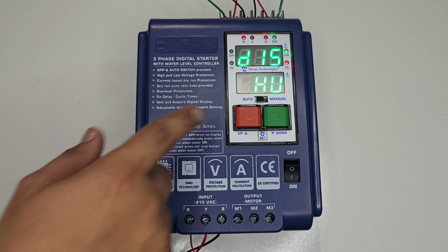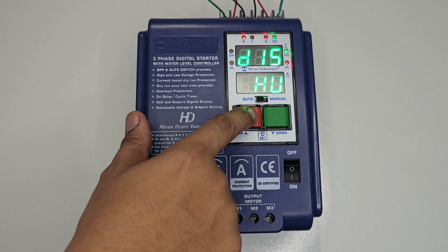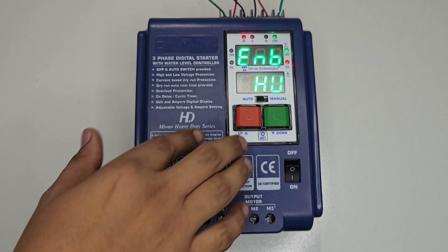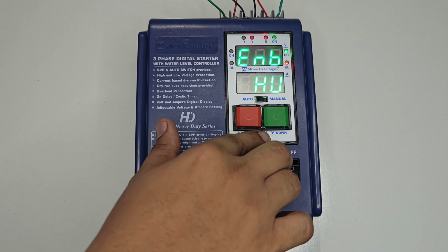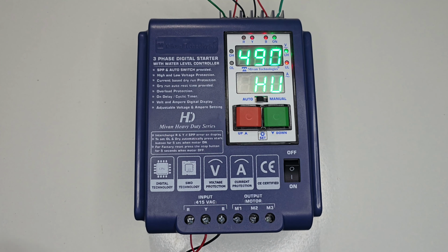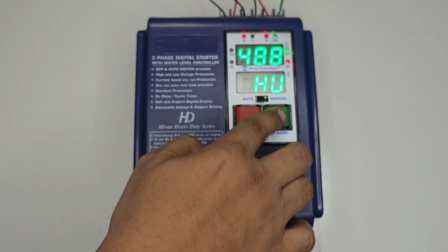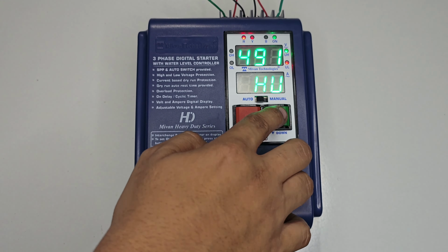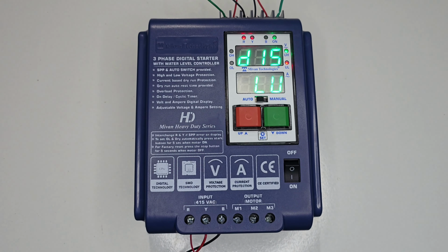Here by the up and down key, you can enable and disable the high voltage protection. Let's enable the high voltage protection. Press the set button. Here you can adjust the high voltage cutoff limit by the up and down key. Press the set button to store the value.